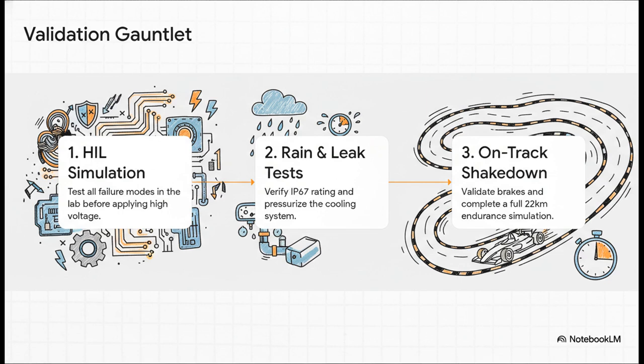A structured testing process is not optional. You have to run the gauntlet. You start safely in the lab with hardware-in-the-loop simulation, testing every fault you can possibly imagine. Then you move on to system checks, like a pre-check for the rain test and a leak test for your cooling system.